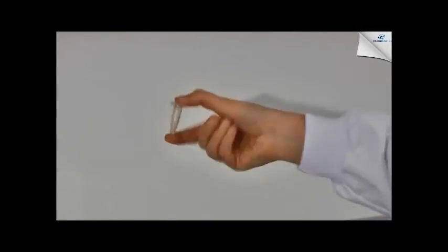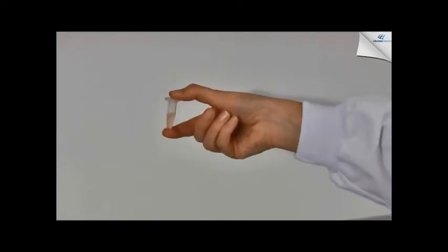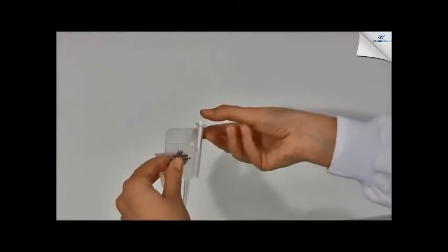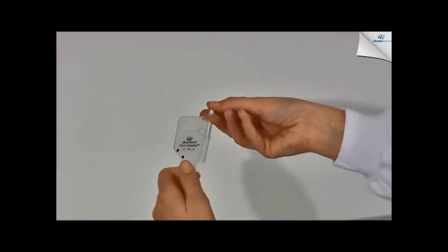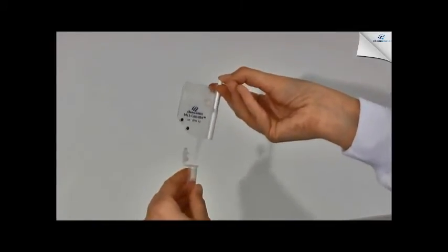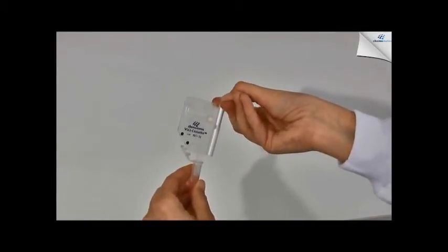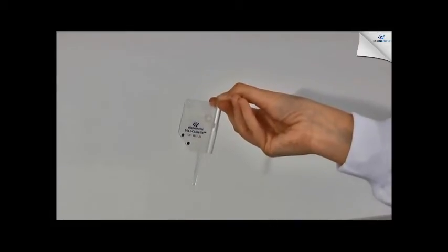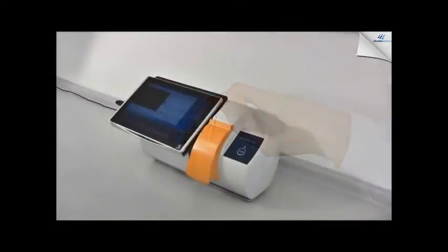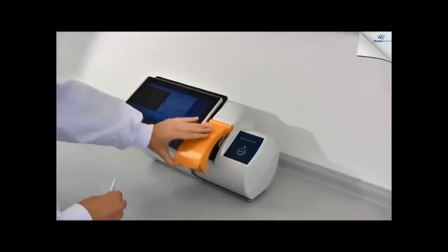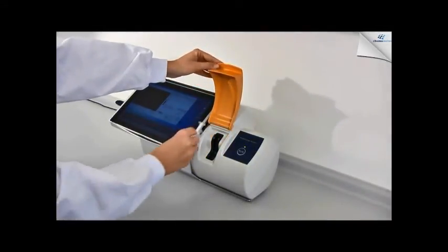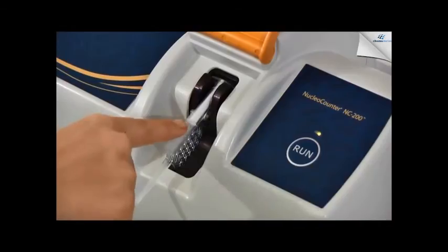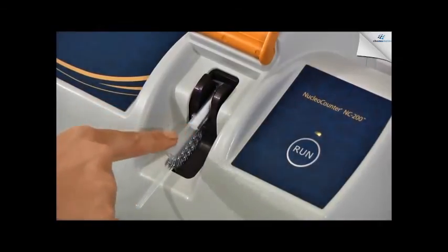First, make sure your cell suspension is mixed thoroughly. To fill the Via1 cassette, simply insert the tip directly into the cell sample and press the piston. Insert the filled Via1 cassette into the cassette slot of the NC200 and press run.